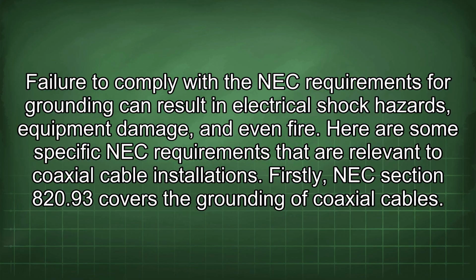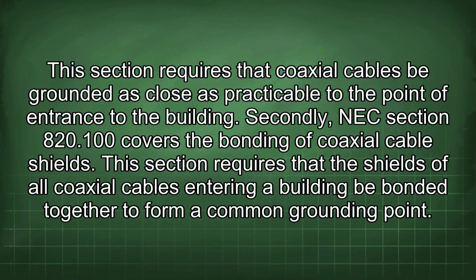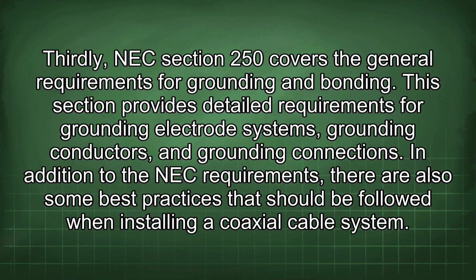Firstly, NEC Section 820.93 covers the grounding of coaxial cables. This section requires that coaxial cables be grounded as close as practicable to the point of entrance to the building. Secondly, NEC Section 820.100 covers the bonding of coaxial cable shields. This section requires that the shields of all coaxial cables entering a building be bonded together to form a common grounding point. Thirdly, NEC Section 250 covers the general requirements for grounding and bonding. This section provides detailed requirements for grounding electrode systems, grounding conductors, and grounding connections.